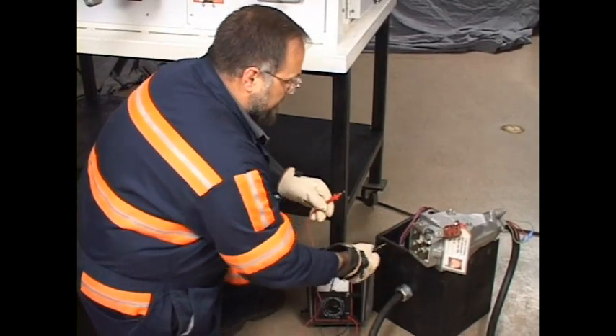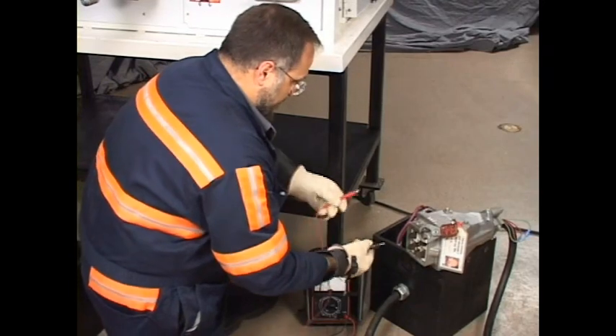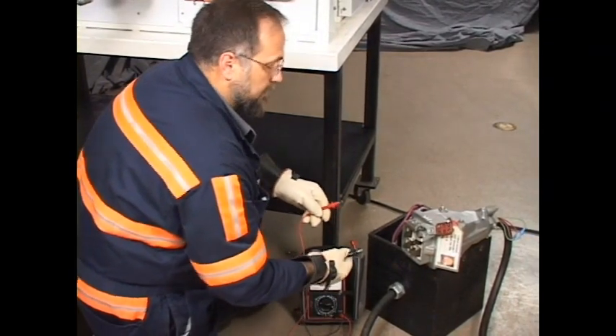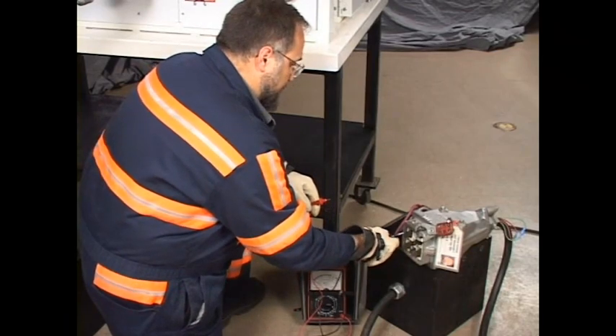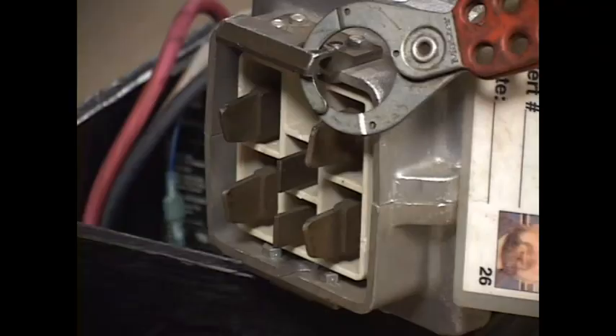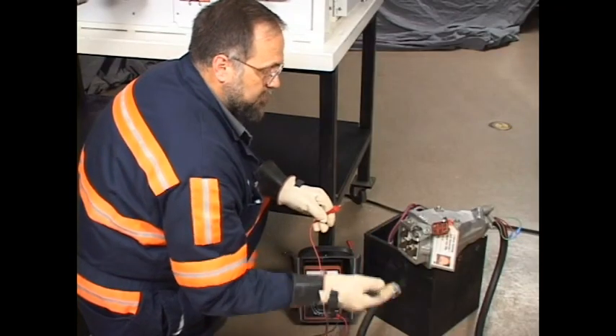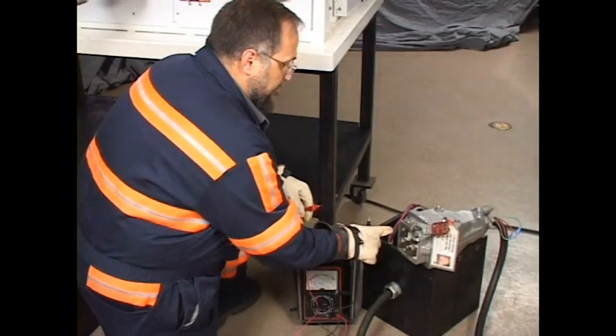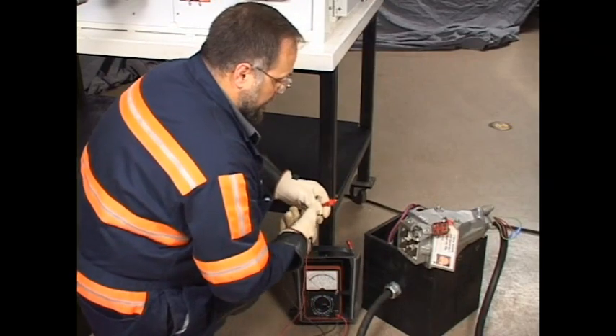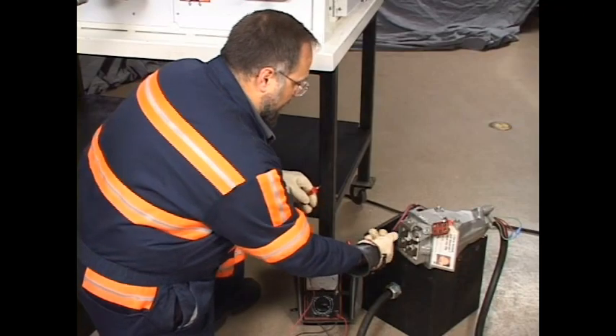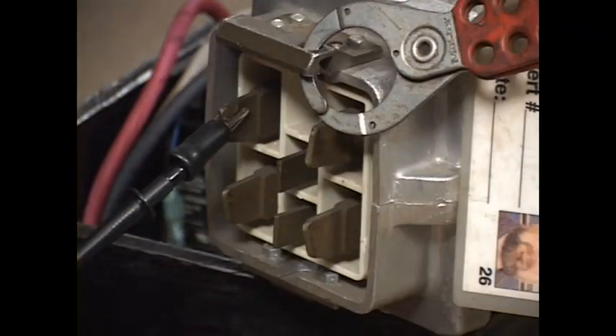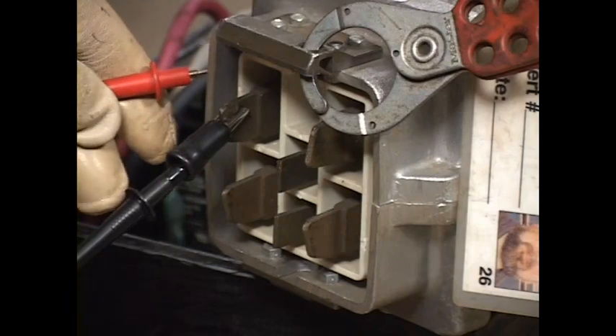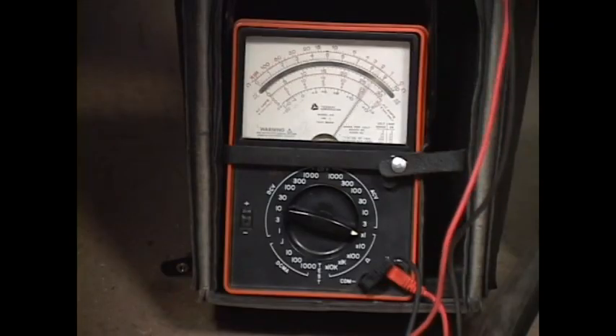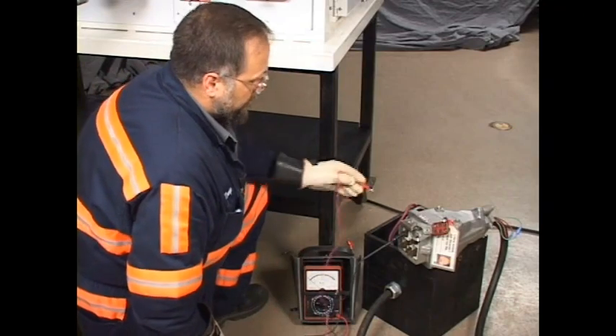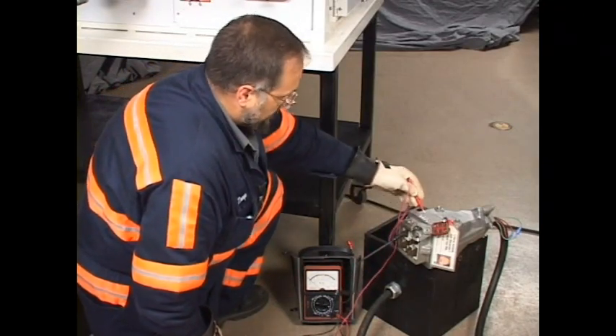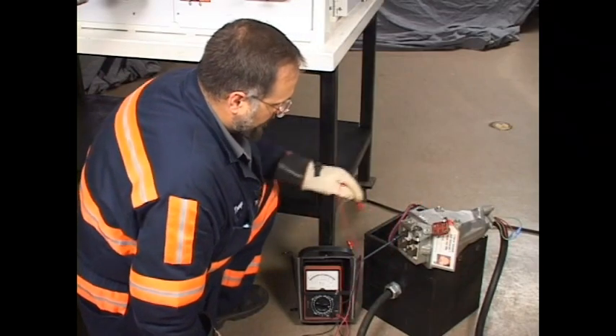Now with all these pins, it's still fairly easy to tell, even, you know, for the novice, which one is the ground conductor. You'll note this one, due to the angle of the blade, is long on top. When the coupler is levered out of the receptacle, this one would be the last one to break, the last one to come away. And by law, the ground conductor in the cable coupler has to be the last. Here we go. Look out. We have a full scale deflection, no resistance. The ground blade is in contact with the shell of the coupler.